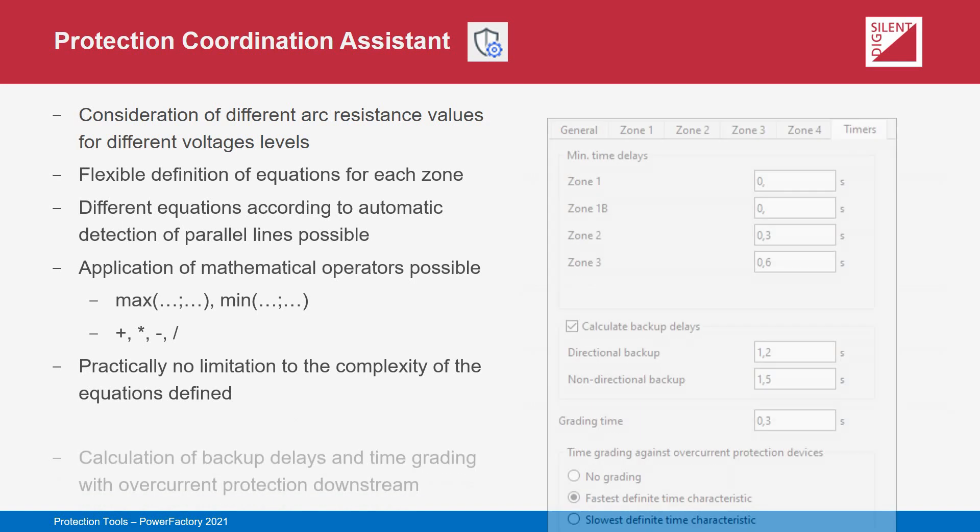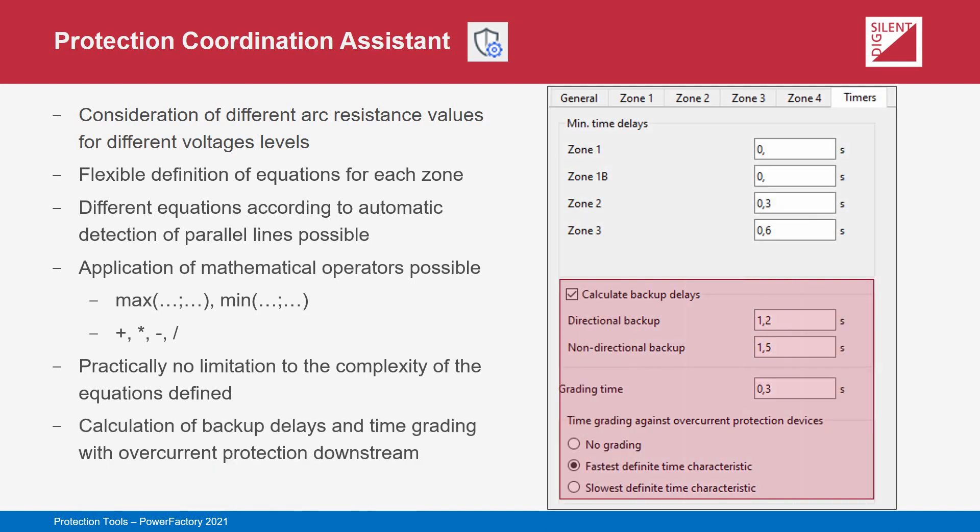Where relays employ directional tripping elements with backup delays or non-directional tripping backup elements — sometimes called starting elements — the time delays for these elements can also be specified. For teed lines supplying a transformer protected by overcurrent protection, specific grading margins for coordination with overcurrent protection can be defined, and the tool will automatically identify cases where this grading time should be applied.